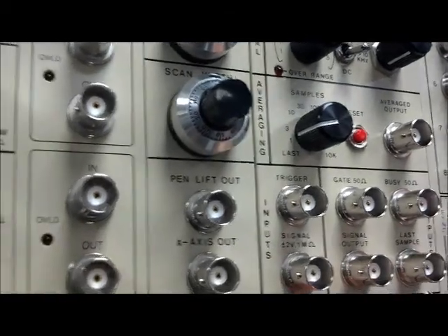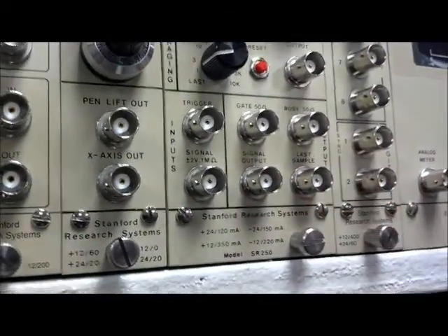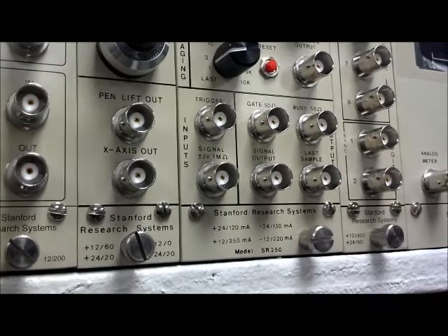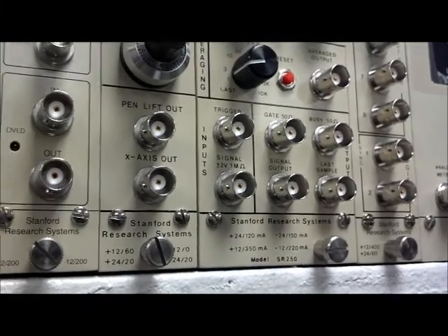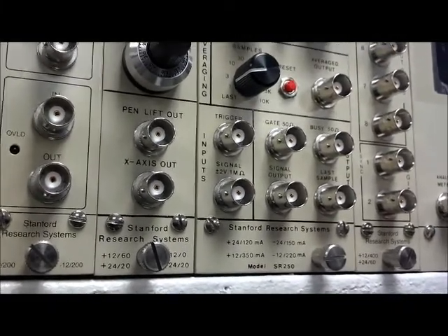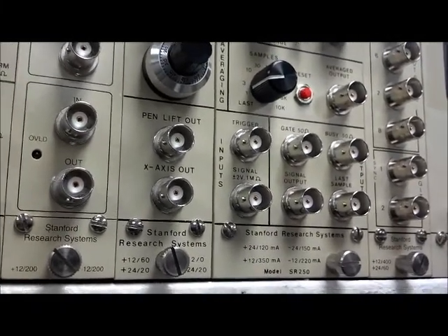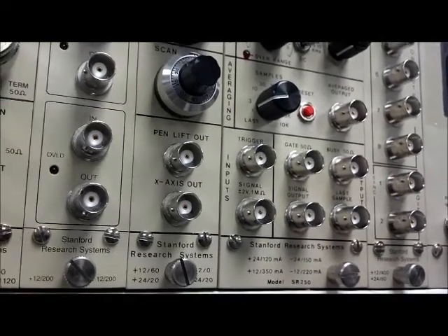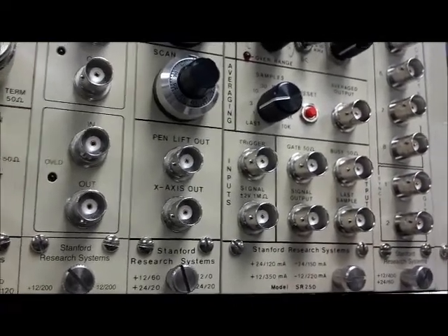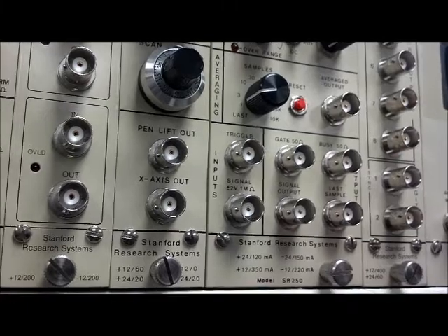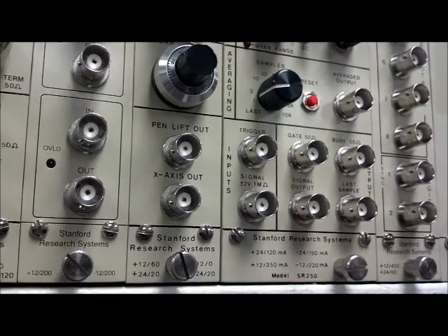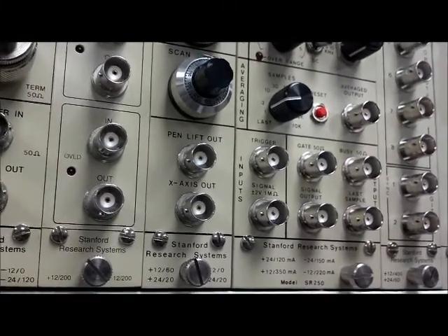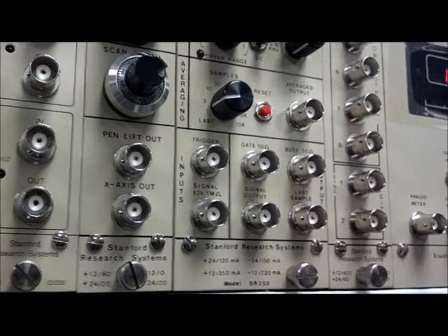We have the input and output section. The trigger portion of the input section is where the input from an external trigger would go. The signal input is how one would get the inputted signal into the boxcar. Under the output section, we have the gate and signal outputs. The signal output BNC is passed directly from the signal input BNC.